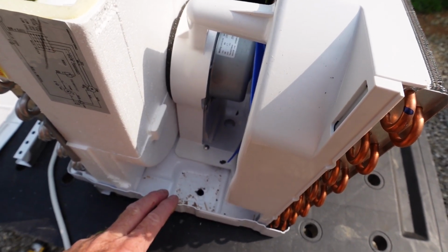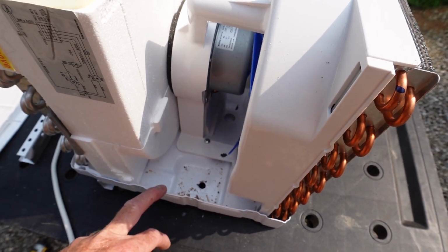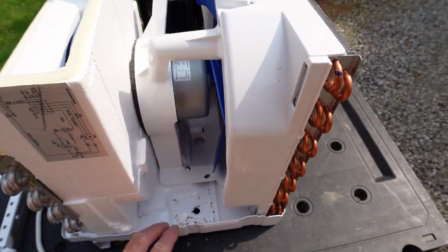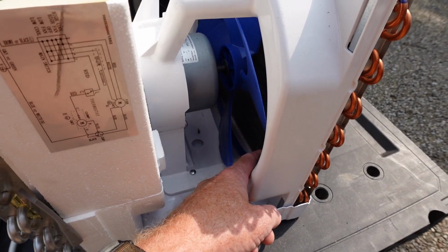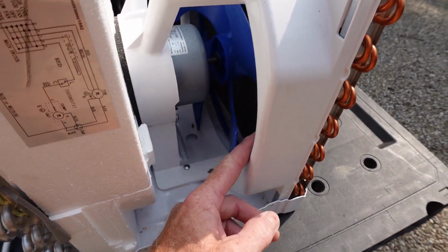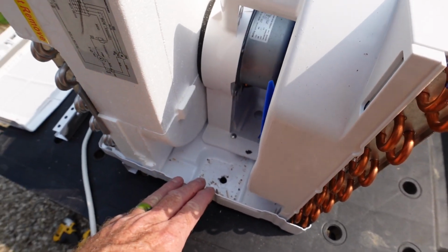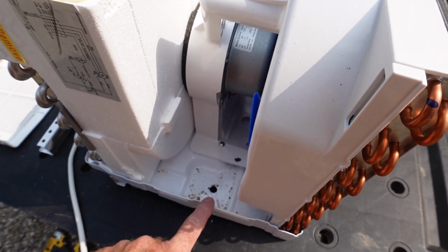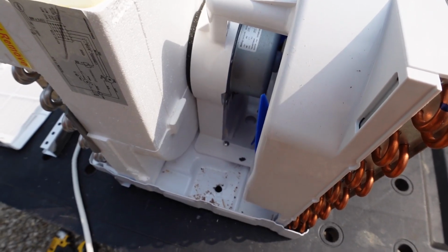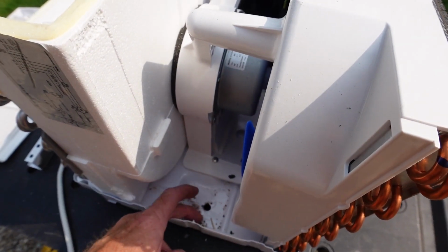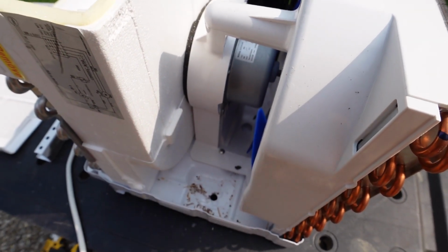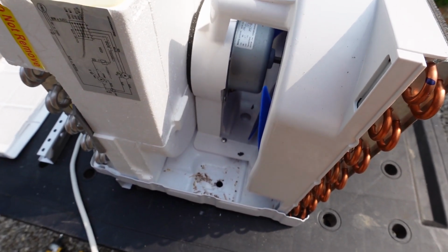So I'm sure they didn't take it apart to drill that hole, but this unit has been drilled to drain the drain pan so that the water was not picked up with the slinger fan, which is right there. There's not going to be any water in there for that to pick up. So that is what I was going to do when I took it apart, was drill that hole, but someone has beat me to it and has already drilled it. And you can even see there's some wood shavings in there, and we all know what that means. So it's getting kind of interesting here.